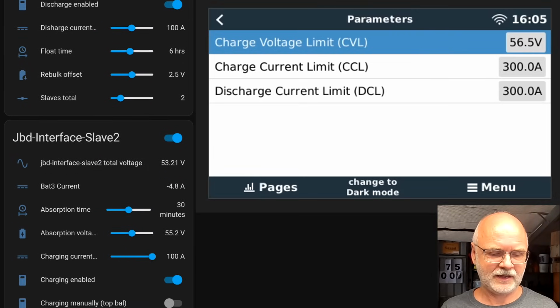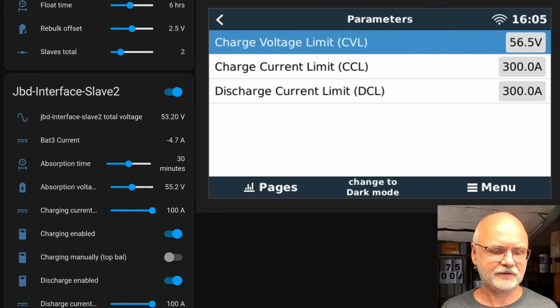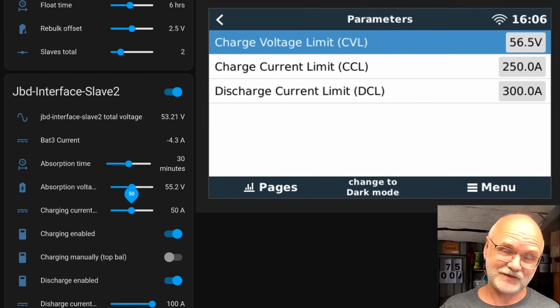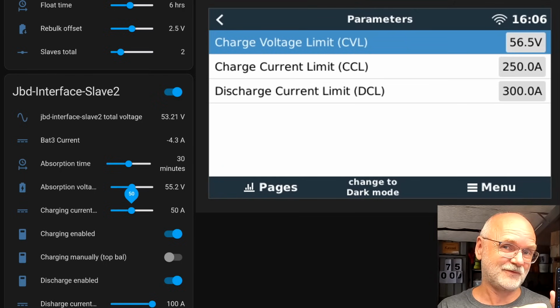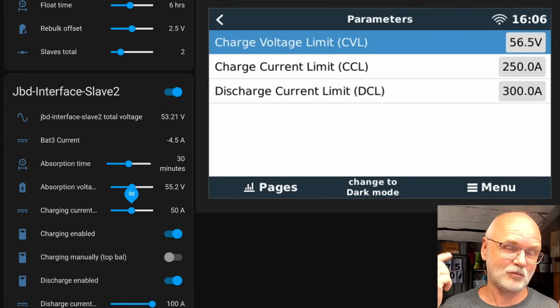And if we scroll down and have a look at the JBD interface slave board, we've got a charging current of 100 amps. If I lower this one to say 50 amps, it will change the CCL from 300 amps to 250 amps. Of course, this does not mean only 50 amps go into the JBD BMS and the other 200 amps go into your remaining battery.